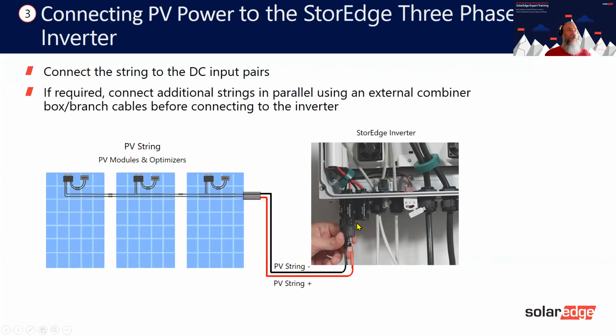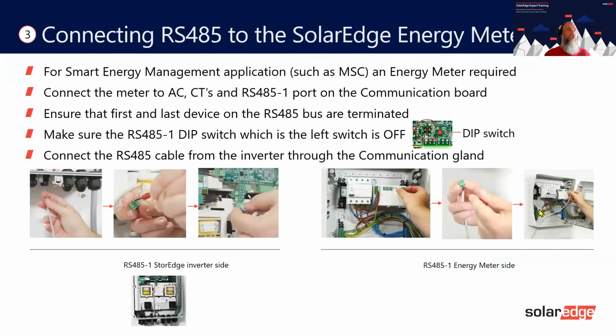So DC, they just push in straight away into the bottom. Nothing special there. The dip switches, they're all in the manual, and it's telling you that basically if you're using RS485-1, you must turn the left dip switch on, or it says off here, so you must turn it up. Okay. What else we've got on here? Just information about the meter, but we're looking at the meter later on, so I'm not going to dwell on it here.